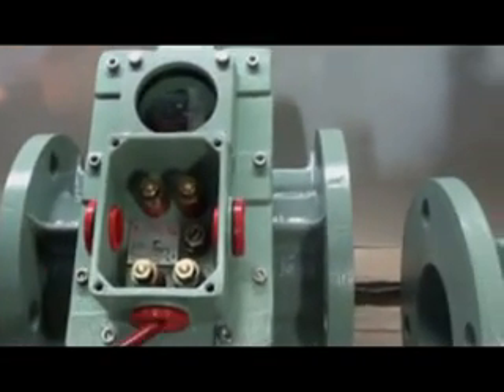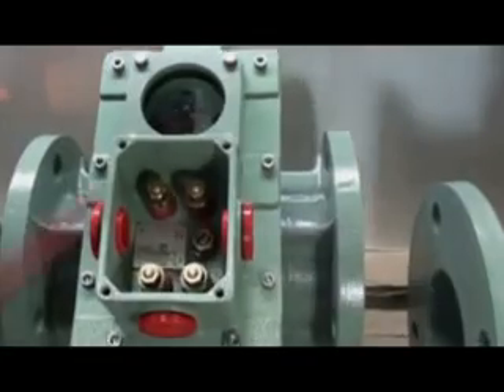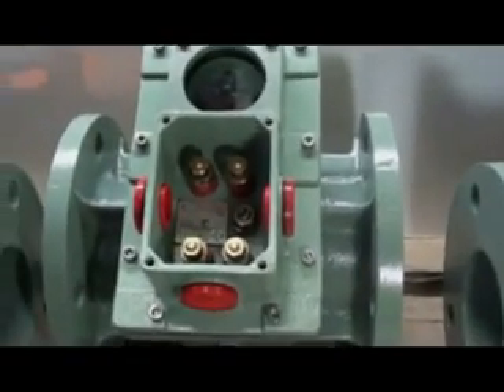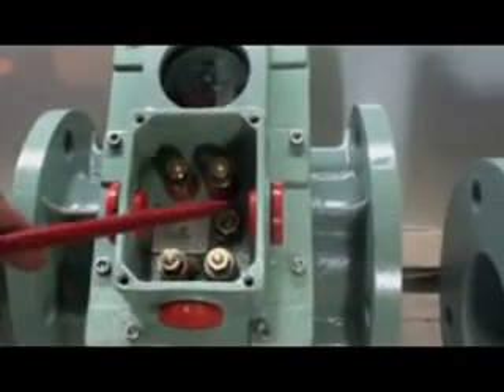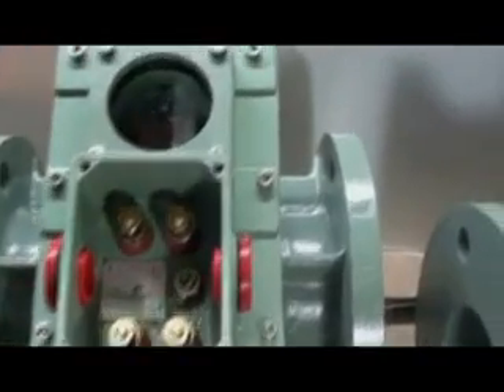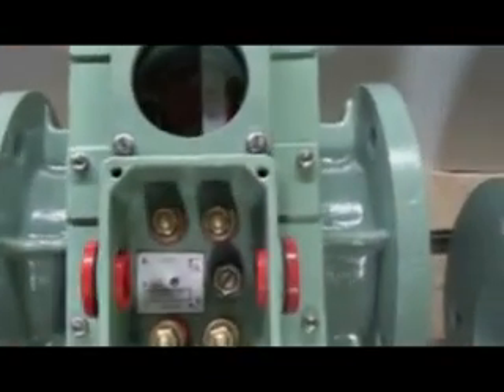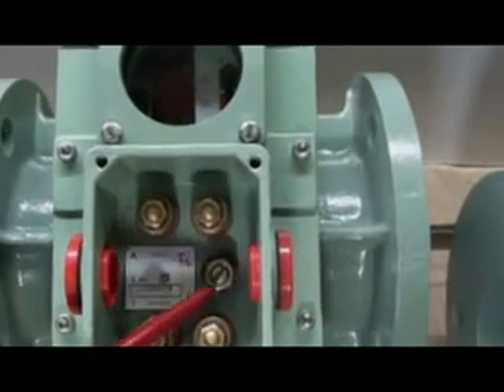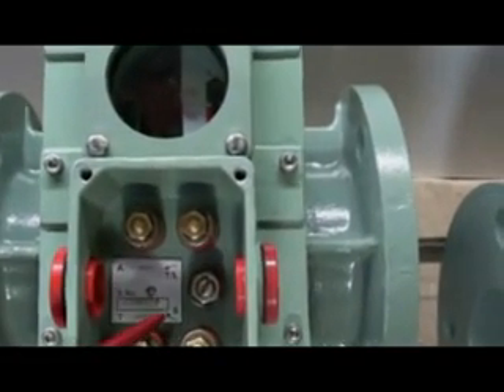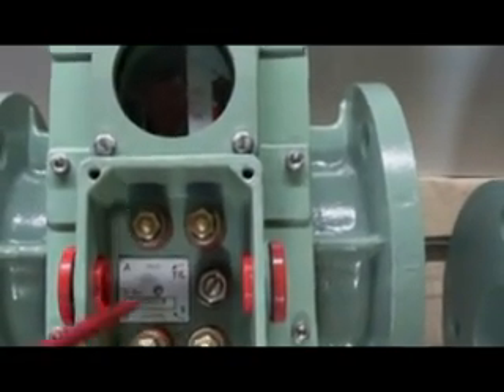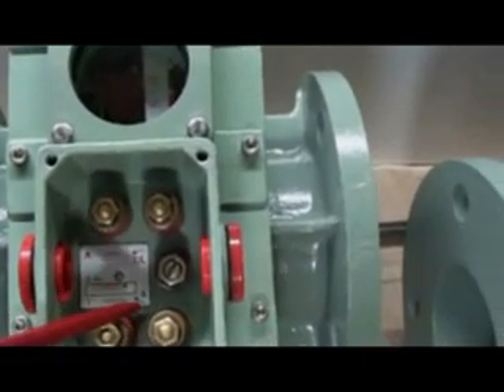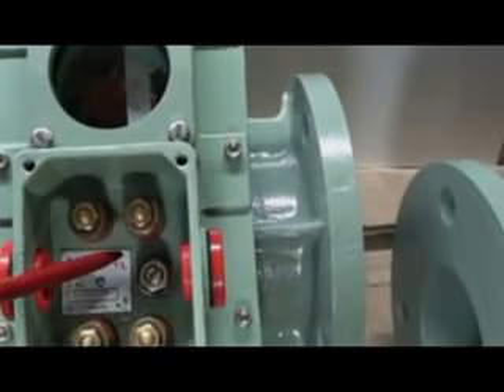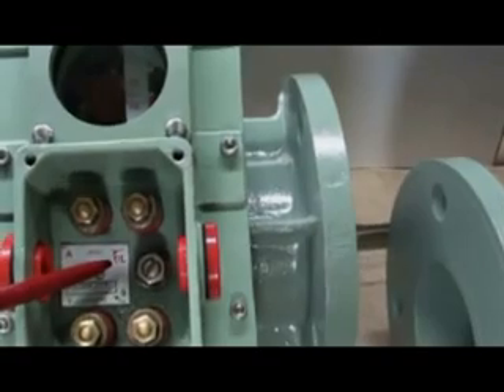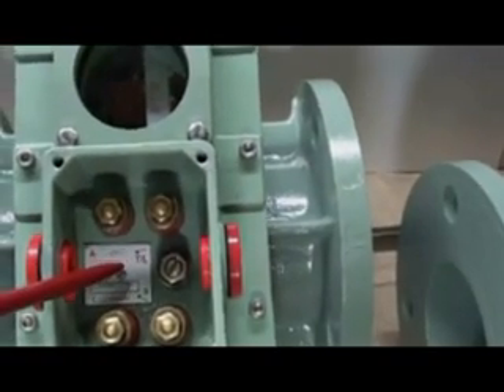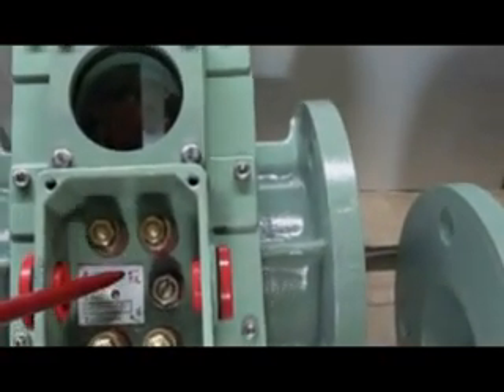There are 3 provisions of cable glanding arrangement: left, right and bottom. We can use any of them. Only the used glanding point's blanking should be removed before commissioning. There is a locking and key arrangement inside the terminal box, and there is a slot in the key. If the slot is towards the S, it means Buchholz relay is in service position, and if it is on the transport lock TL position, it means Buchholz relay is in lock position.